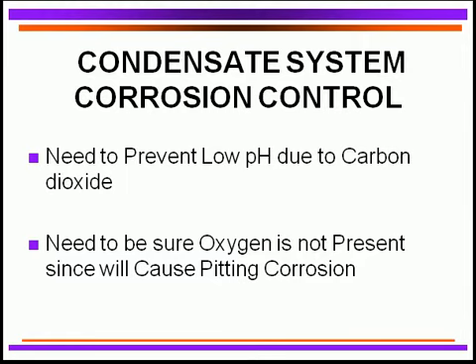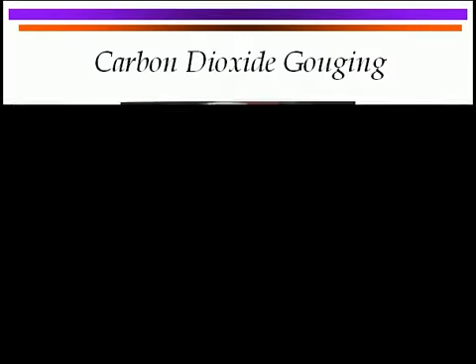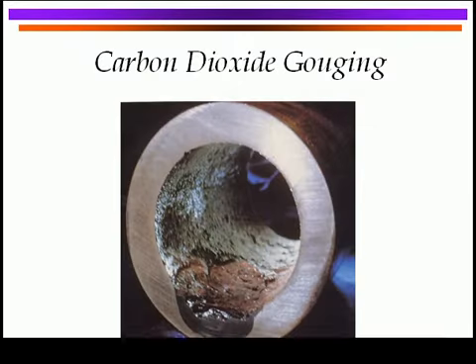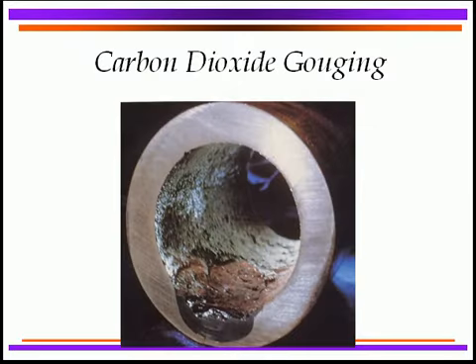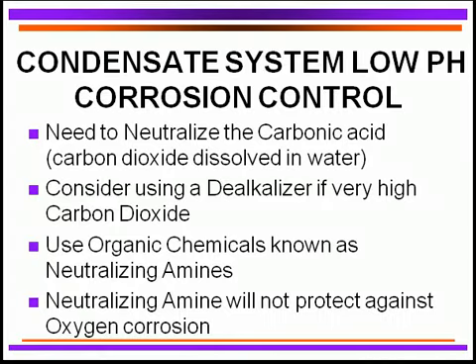The most common issue is carbon dioxide, so let's talk about that. Here's the type of corrosion you can get on a tube — it's literally like a river of condensate passing through with low pH, and it tends to dissolve the steel or copper lines in the system. What we need to do to prevent this low pH in the condensate system is to neutralize the carbonic acid.